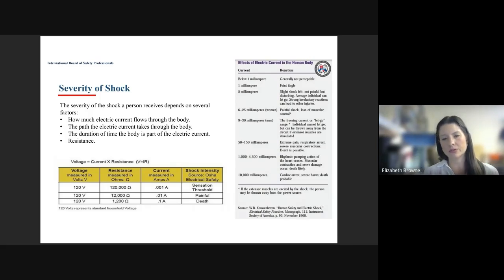So you can see that all of these measurements in current are in milliamperes, or milliamps for short. So a milliamp is a 1,000th of an amp. And so it does not take much current flowing through a person's body for a person to experience extreme pain, respiratory arrest, and possible death. If you look in this range of 50 to 150 milliamps, and just to give you an idea of what that means, a typical handheld power drill has about 75 milliamps of current flowing through it. So that kind of gives you an idea of a typical item we might use in a workplace that can cause extreme hazards and injury and potential death to employees. So we need to be very sure that we're taking care of our equipment, it's in good shape, and employees are not handling equipment that is damaged or in a way that they should not.